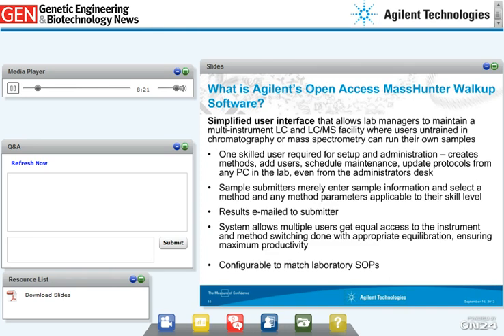The Agilent MassHunter Open Access LC-MS software for biopharma is a simplified user interface that allows lab managers to maintain a multi-instrument LC and LC-MS facility where users not trained in chromatography or mass spectrometry can run their own samples. It requires one skilled user for setup and administration. This superuser creates and optimizes methods, adds users, schedules maintenance, and can update protocols from any PC in the lab. Sample submitters merely enter sample information and select a method. Once the run is complete, results are automatically generated and emailed to the submitter.